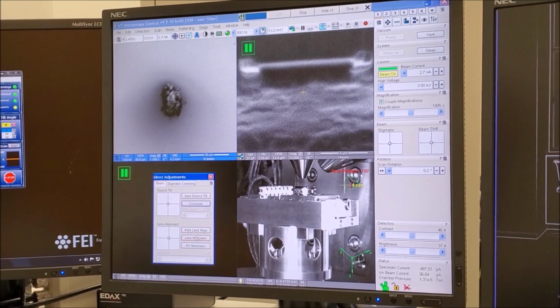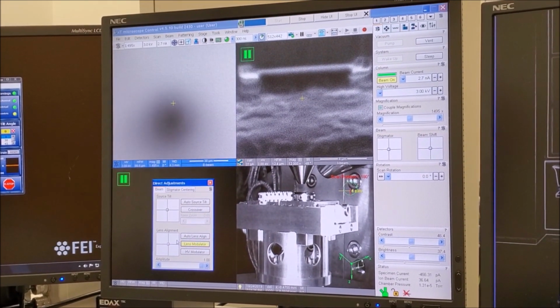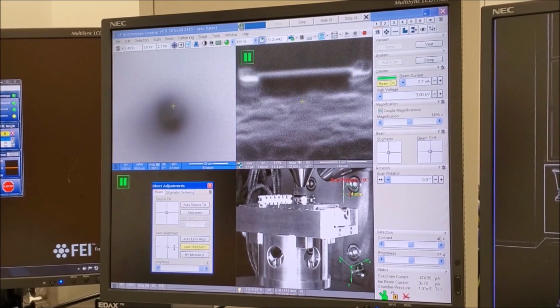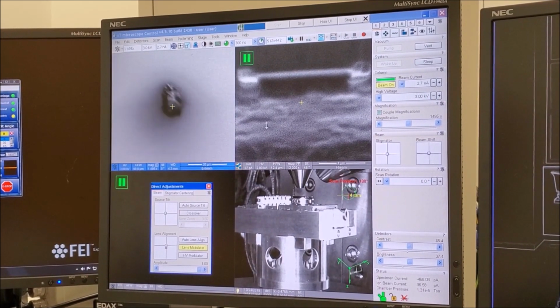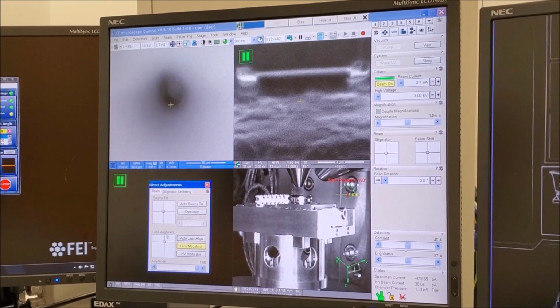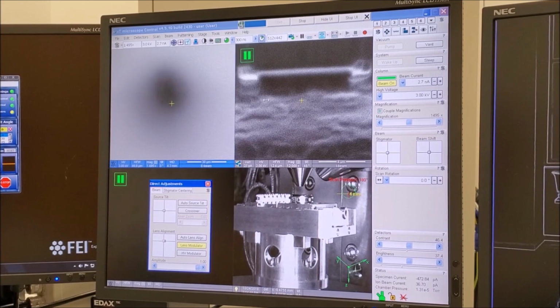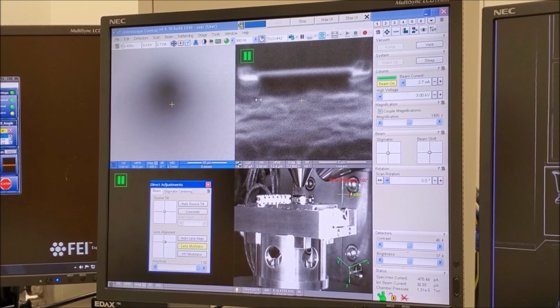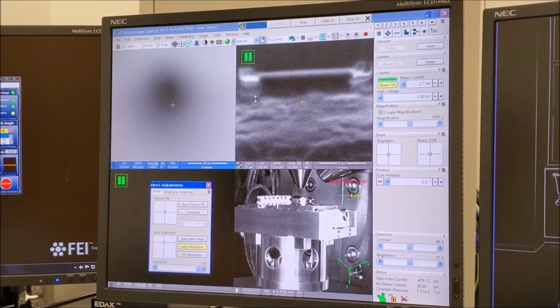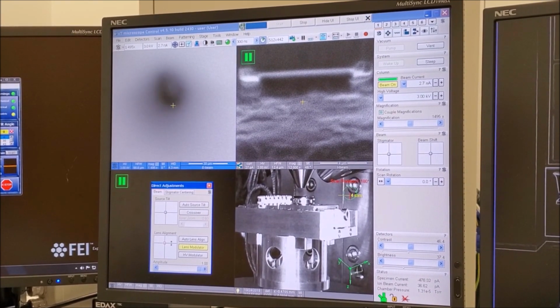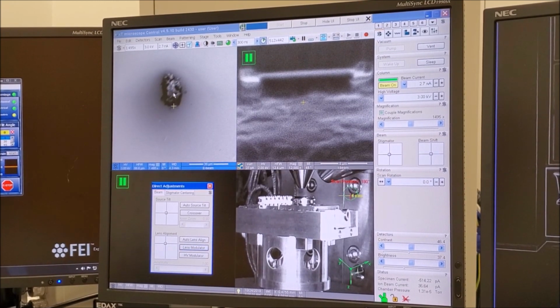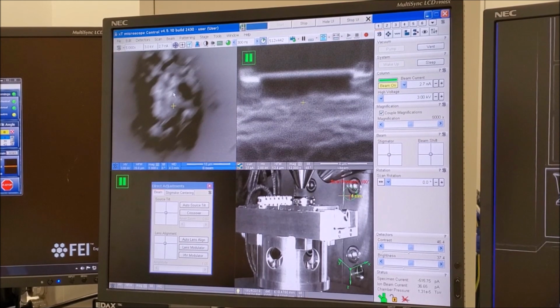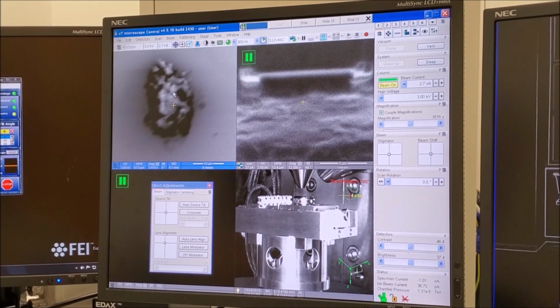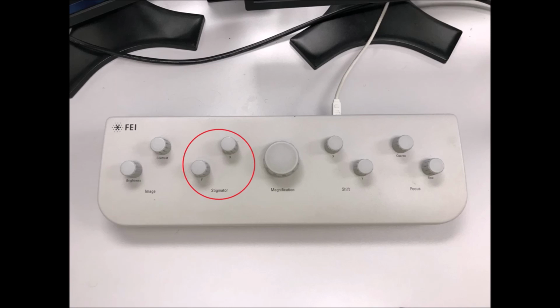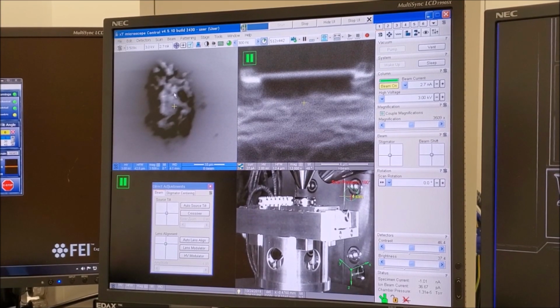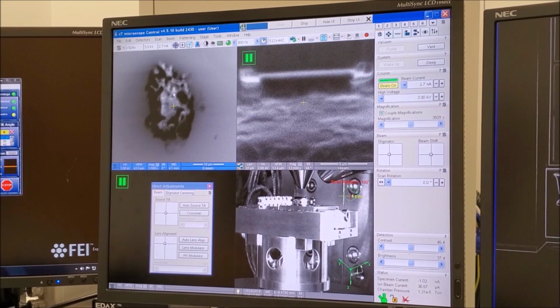Select Lens Modulator to modulate the strength of the final lens. Then use the crosshairs under Lens Alignment to minimize shifting of the image as the image goes in and out of focus. Once shifting of the image has been minimized, select Lens Modulator to turn off the modulation. Then focus the image and then use the stigmator knobs on the knob set to obtain the sharpest image possible. Note that this is an iterative process and you may need to refocus and restigmate several times to achieve the best possible result.